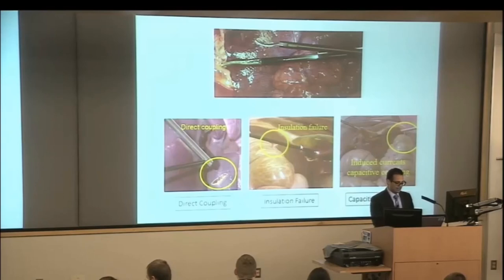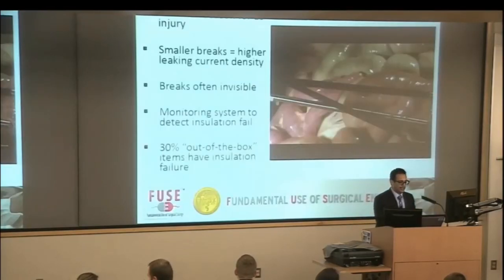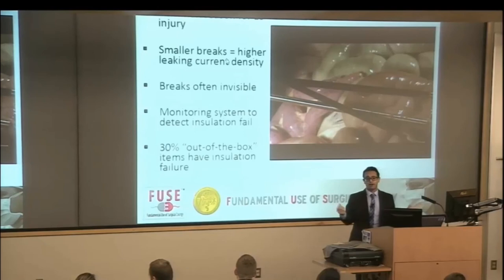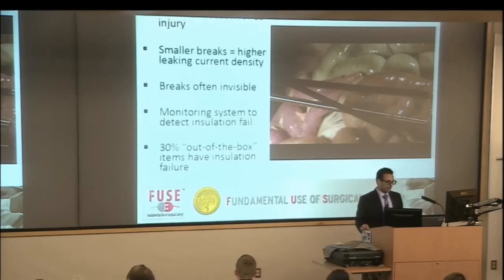Another one is insulation failure. Obviously we're using long instruments that are insulated. We assume that it's fully insulated, but oftentimes it's not. And actually, there's good evidence that even new instruments you take out of the package have breaks in insulation, and this can leak current outside your field of view.